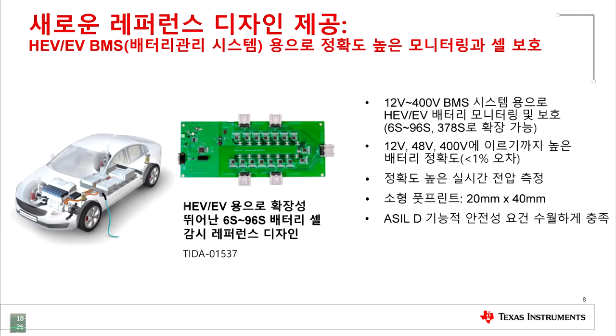So the reference design supports battery accuracy across all battery voltages, whether this is 12 volt, 48 volt, 400, or anything in between, with less than 1% overall error on the cell voltage measurement. Very important point: the cell voltage measurement is a key parameter to be measured. It needs to be accurate and simultaneously measured.